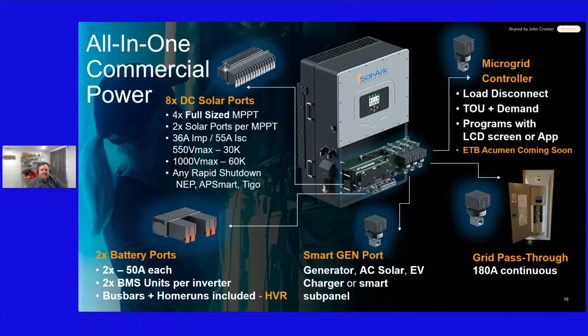We're going to talk about this GEN port - this is why the architecture is so great for AC coupling, since that additional interconnection point lets you land AC coupled solar directly onto it. Many of our customers just choose to utilize the DC solar because it's there, and that ends up being more cost effective, though for commercial the math might be a little different. If you want to use certain AC coupled inverters on a commercial rooftop, you can put the battery inverter next to the battery and those rooftop inverters, and have that be your interconnection point.